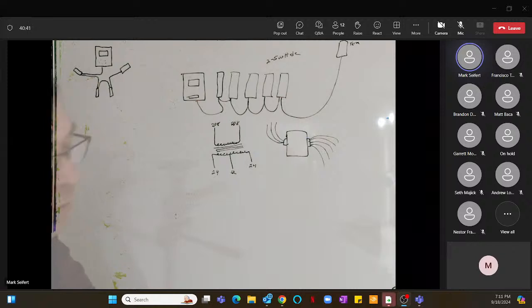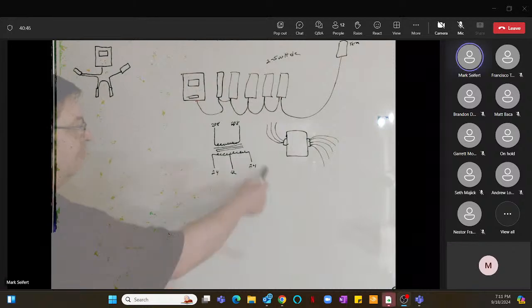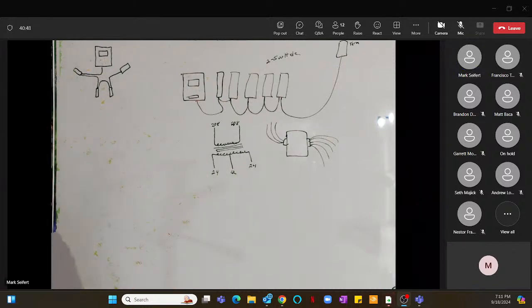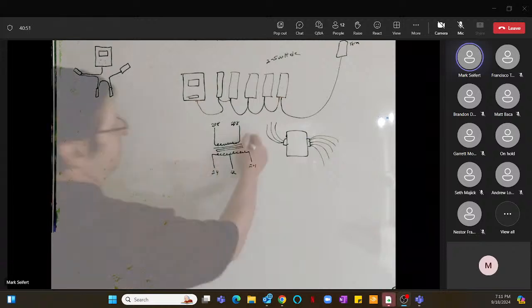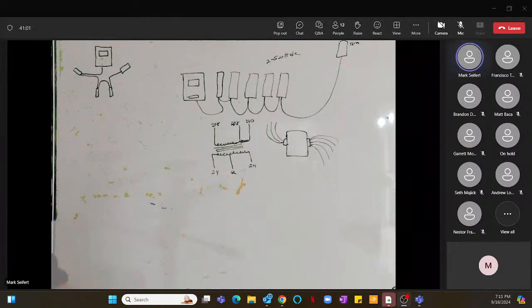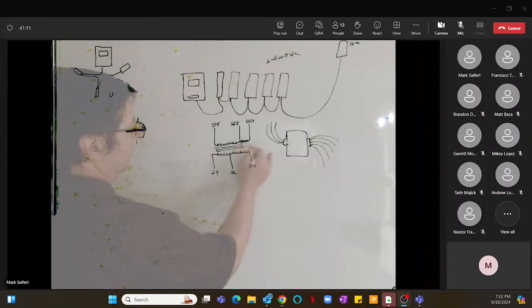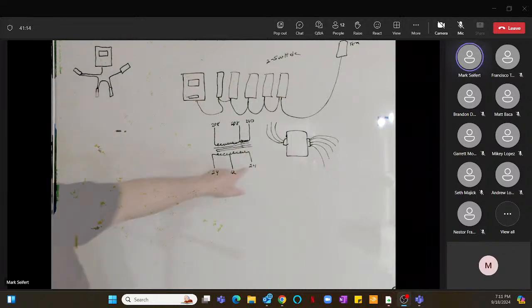If you hook it up to the 240 side, your voltage coming out is going to be too low. Won't be enough voltage over here, because the 240 is going to be more windings. So if you hook up 208 to the 240 side, it's going to be a weaker field through the iron bars, meaning you're going to have less voltage on the output. So that's one thing to keep in mind.